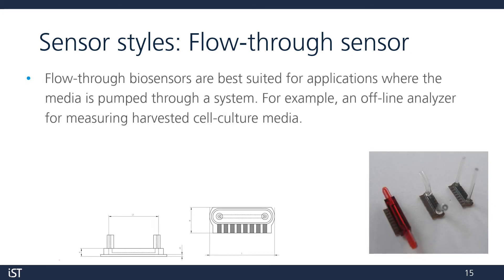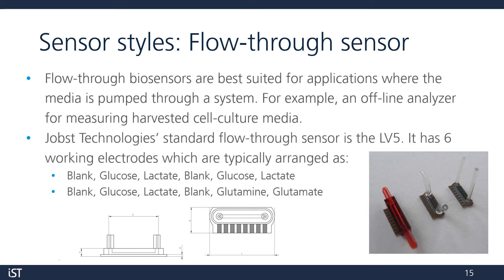Next, we have our flow-through cells. The flow-through biosensors are best suited for applications where media is pumped through a system — for example, an offline analyzer for harvested cell culture media. The LV-5 flow-through sensor is available with a few different flow cell geometries and has two standard electrode arrangements. First, we have blank, glucose, and lactate electrodes, two of each, giving us two glucose and two lactate concentration outputs in our software. Next, we have the 4-analyte LV-5, which gives us glucose, lactate, glutamine, and glutamate concentrations, all on one chip.